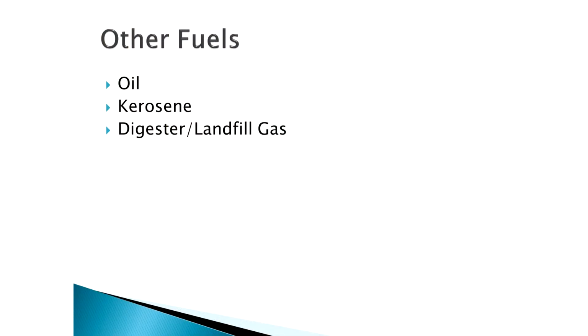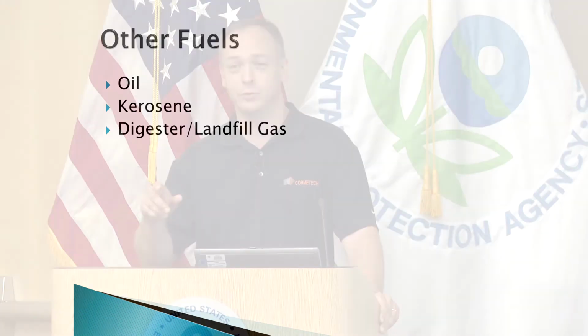So then the other fuels. I just talked about oil just a bit. In this country, generally we're talking about number 2 diesel. It's low sulfur. There is an SO2 oxidation reaction for SCR catalyst. It's fairly straightforward: SO2 plus oxygen gives you SO3. The SO3 is bad. It tends to promote the ammonium sulfates more than the SO2. You see that some with oil, and in these cases controlling that SO2 oxidation may be desirable. Normally that hasn't been a significant factor.